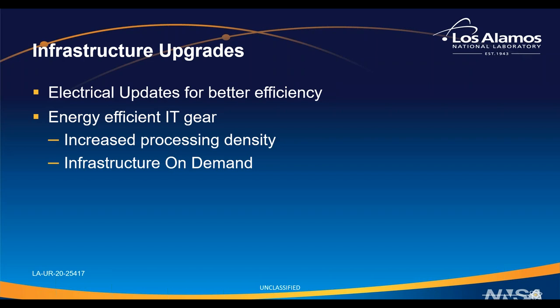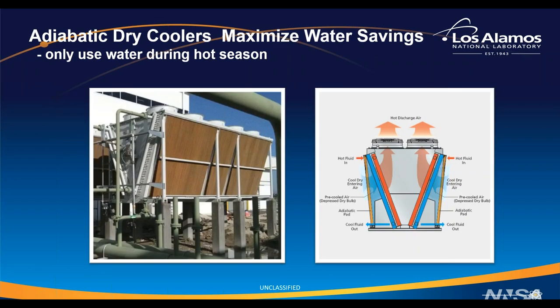Next slide. The next slide is a picture of adiabatic dry coolers, which can be used to maximize water savings. On the left you can see what an actual adiabatic dry cooler looks like, and on the right is a diagram showing how it works. The big advantage of this is it uses very little water in our climate, about one-eighth of the water required for an evaporative cooling tower.